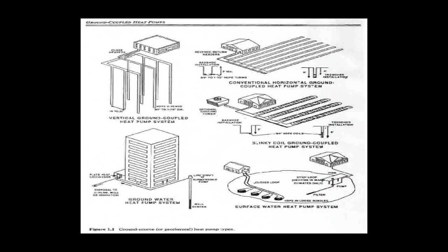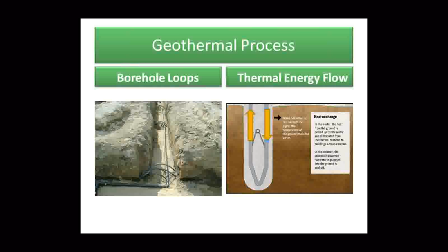The type of system is a closed loop. You can see in the left photo here, before it was covered over, the boreholes spaced 15 feet apart. They're headered together, and with this cross-section we're flowing water into the ground through this piping system and back out, so it's just circulating through the ground. Its sole purpose is to transfer thermal energy, either into the ground or back out, depending on the time of year and the load on campus.